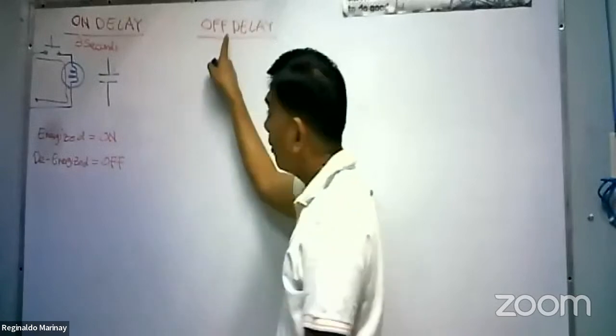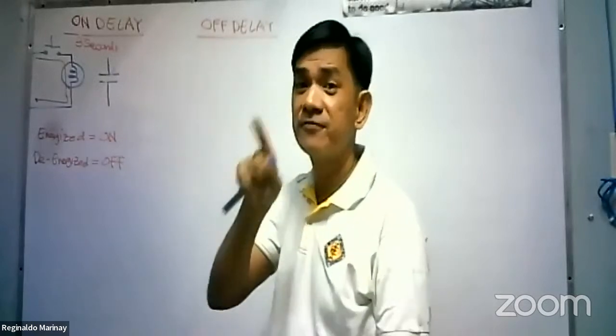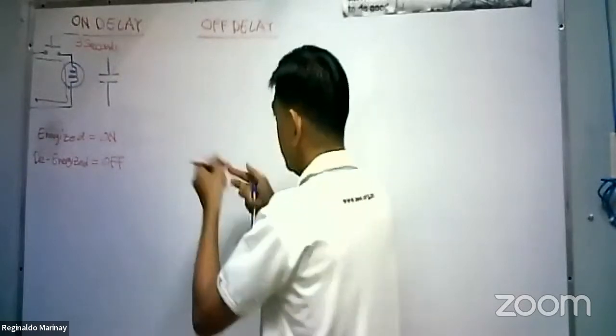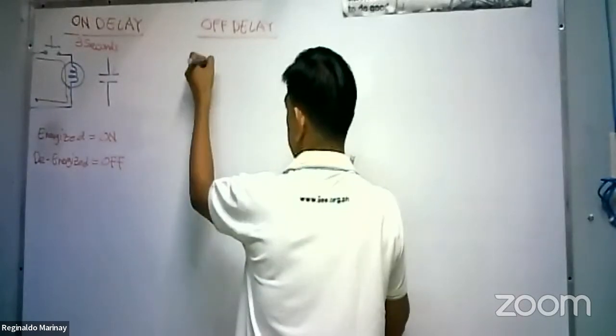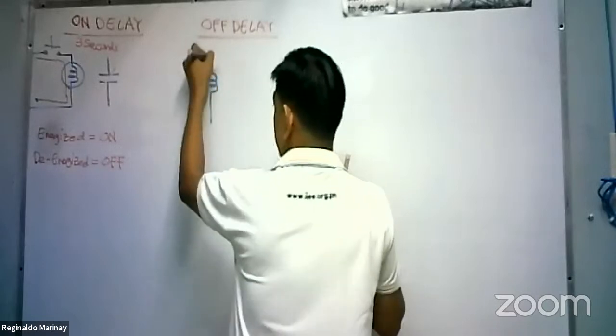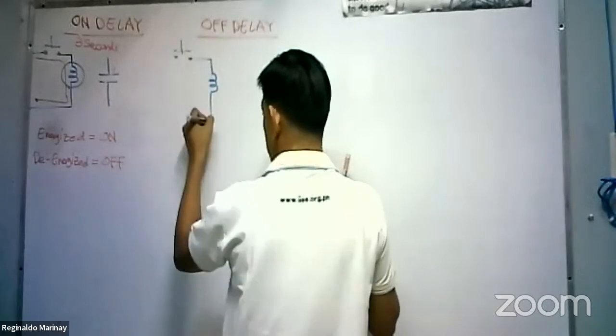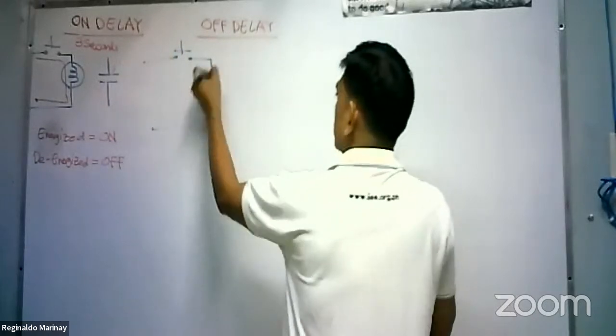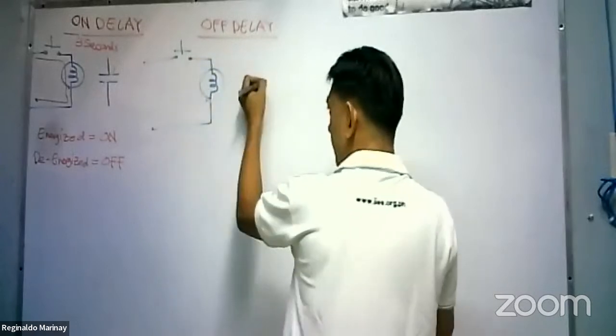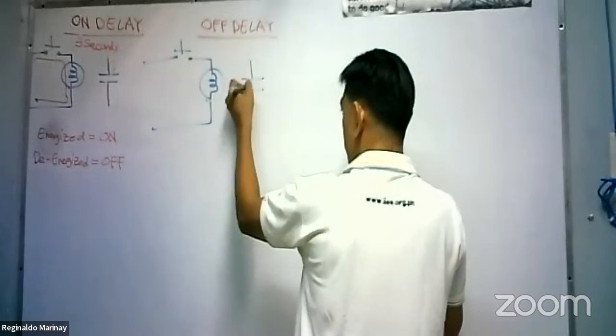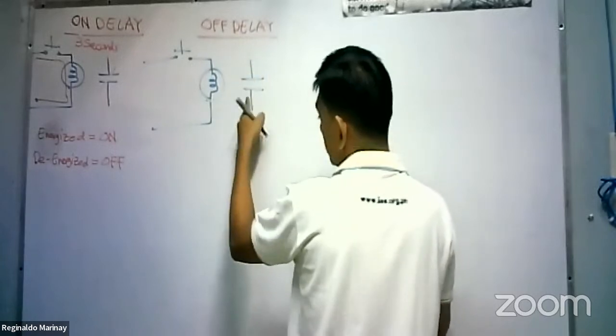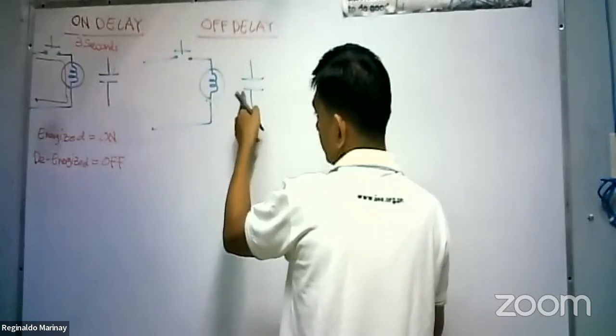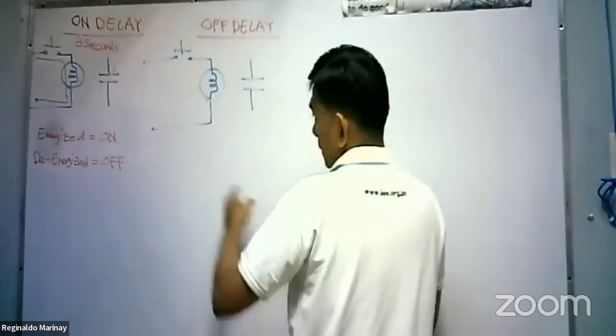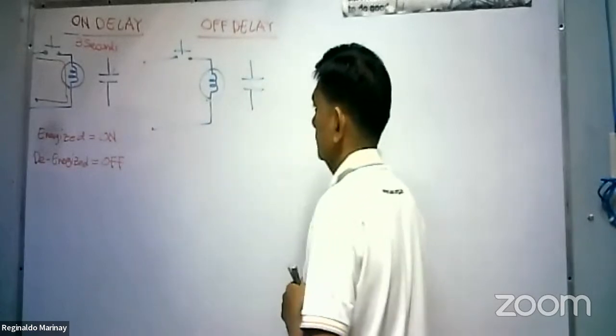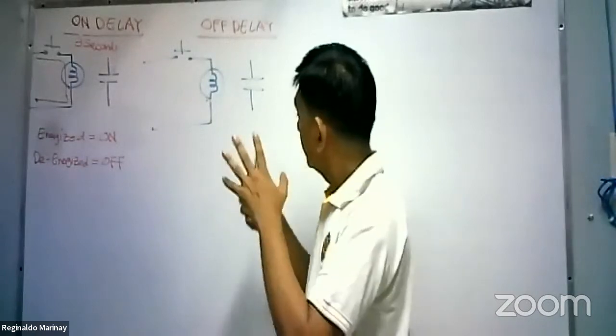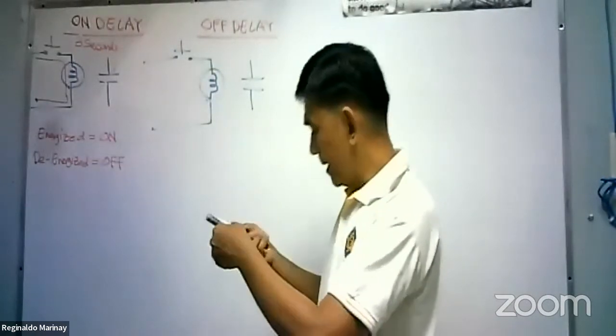Let us go now with the off delay operation. What is now off delay? This is the basic operation of the off delay. This is the holding coil of the off delay relay. Okay. Again, this is the holding coil. You see the coil there. And we have here the normally open push button. Normally open contact, sorry. This is normally open, of course. See? You have your line 1, line 2. Okay, take a look. The off delay relay, no?